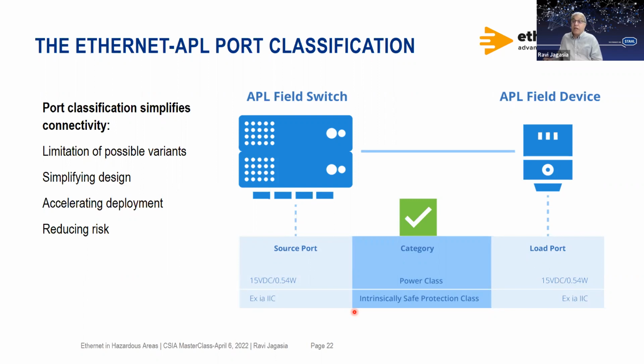Entity parameter loop verification. You would remember in the Foundation Fieldbus days, we wouldn't have to do much of that because the standards allowed for this entity parameter to be standard across all vendors. And then the field device also complying to those similar standards. So you had the common protection class. So this is what the port classification was. It limits all the variants. It simplifies your design. Deployment becomes easy, and it definitely reduces risk when you're working with multiple vendors, when you are trying to build a design and you are then qualifying your standards and your solution based on certain standards.